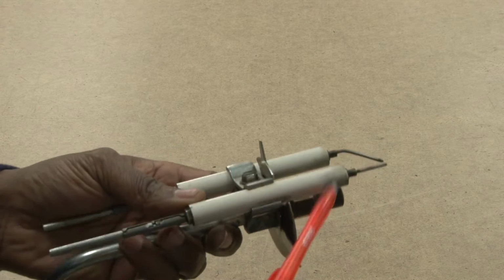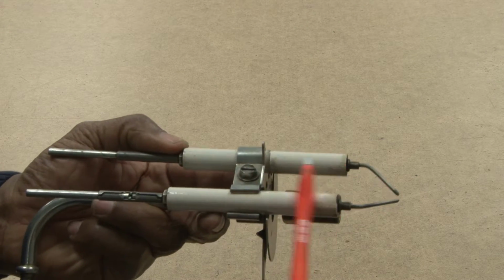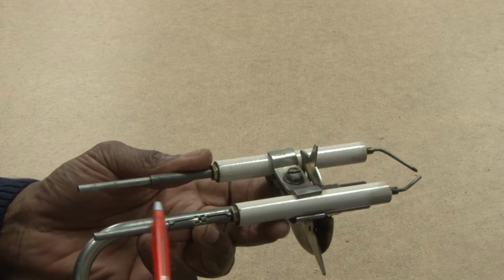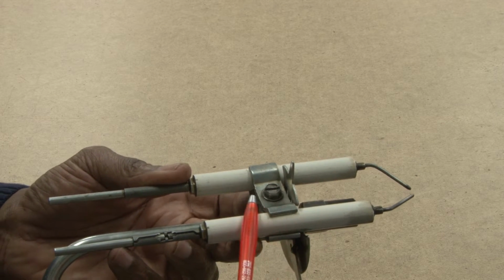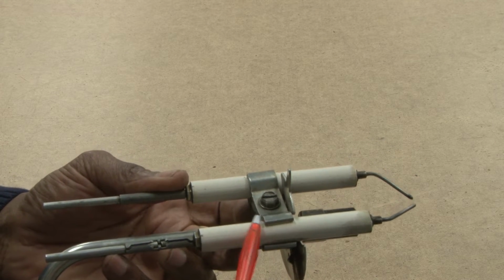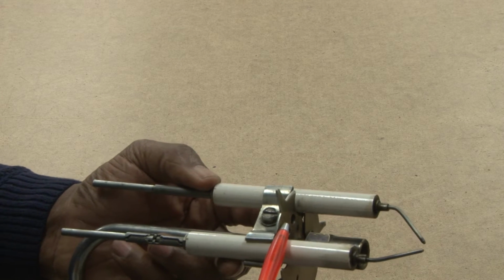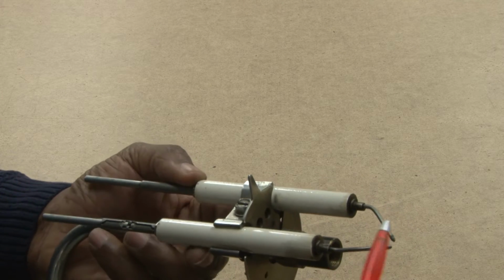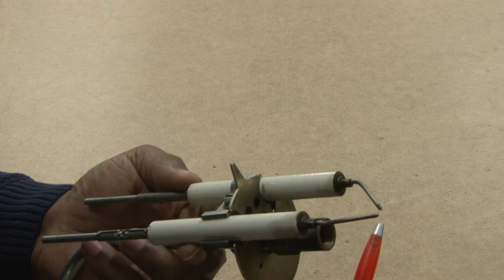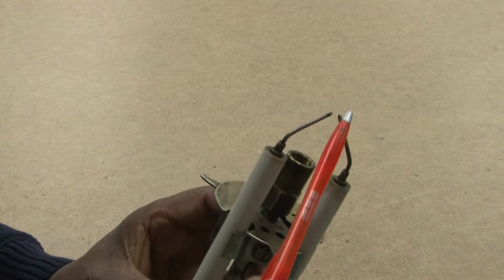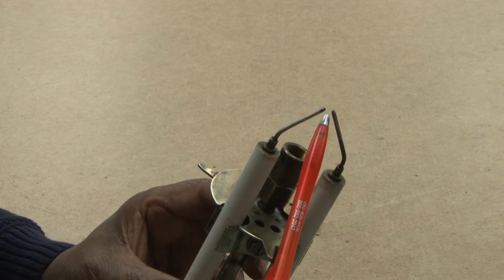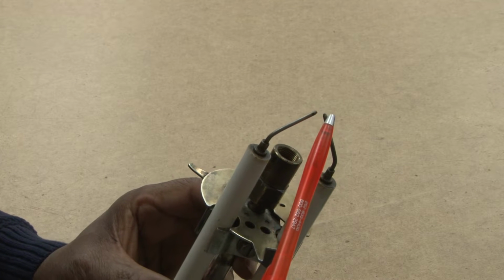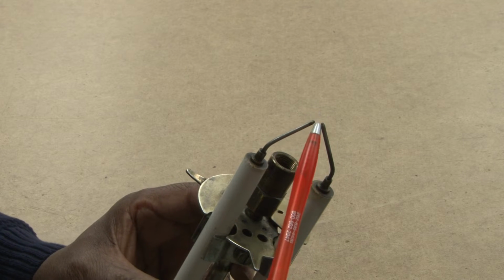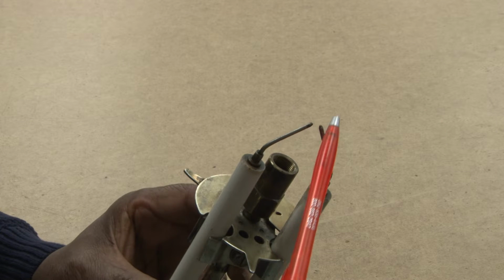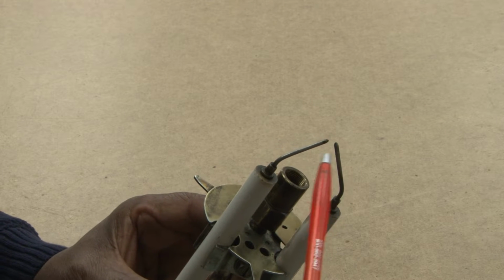It will have a ceramic coating over the rods to insulate it from the cabinet or anything, to keep it from shorting out. So the current will flow to the end of the electrodes. There will be a spacing between those 2 points, and it will cause a very large spark to form between them, and because of the blower, it will actually come out from the electrode.